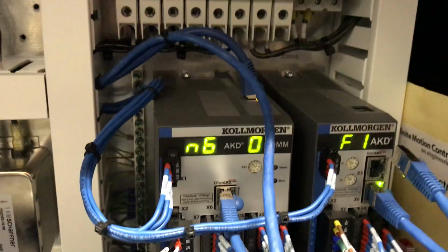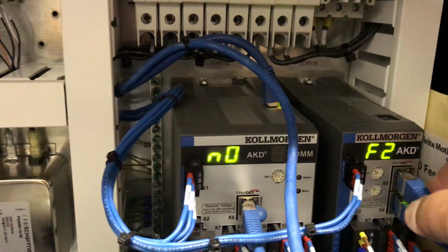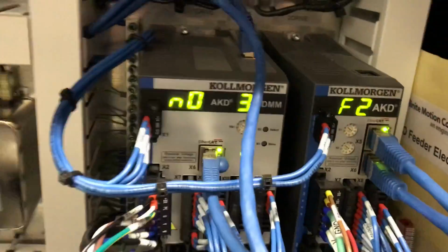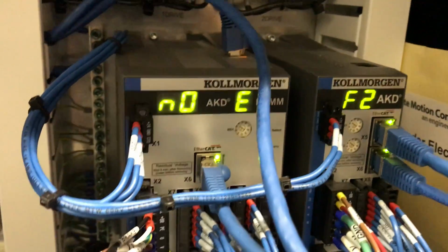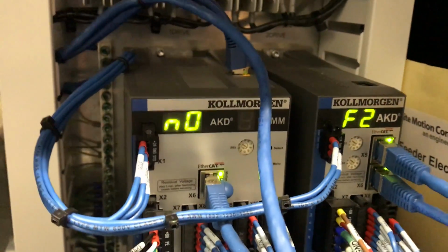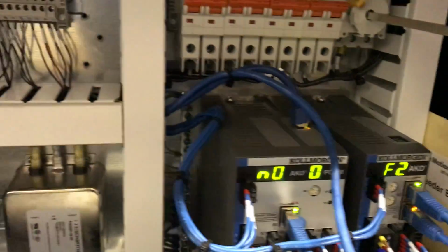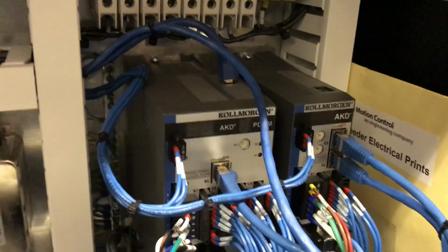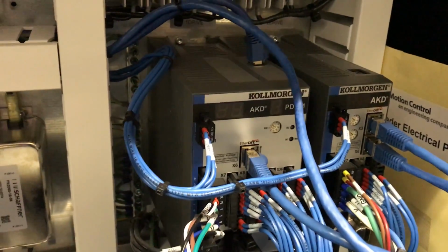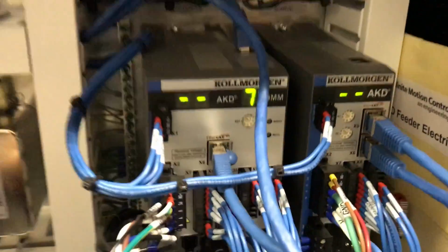Now we have this E33 fault. I'm going to restore communications to the proper communications connections. Now this fault can't be cleared. We have to cycle power. So I'm going to turn power off to the system. And now I'm going to turn power back on, and we can see what happens during startup.